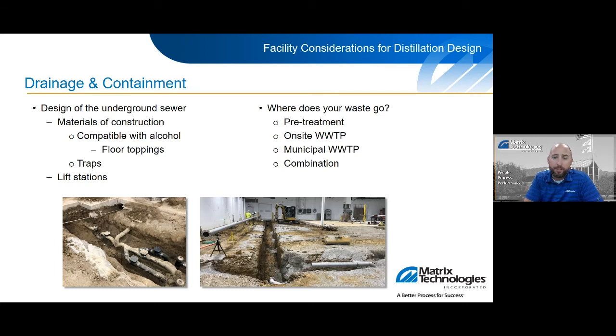The other thing to consider is how you are transporting this. I've seen lift stations used to transport this waste material. One thing to take into consideration with that is the redundancy of the pumps. You always want to have a backup. You also have to consider that these are classified spaces, so your rating is going to be Class 1 Div 1. What I've seen in the past, and I like this, is putting a stack light or beacon up there to let your operators know that the pump is functioning or if there's a fault on it. So it's a good visual for them without physically checking the float to make sure everything's working.